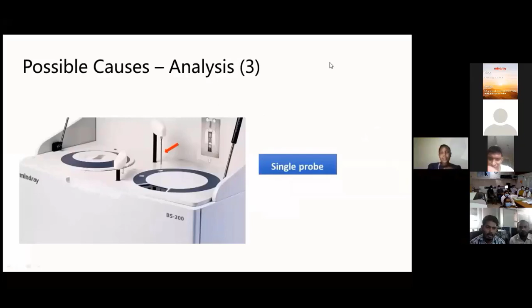There's always one who knows better than you sometimes. So we sought help from the distributor engineer. But no fault was found on site instrument checking. The instrument was okay, calibration okay, everything okay. Now, the engineer noted that the detergent was not original. It seemed the quality was not okay, and therefore he recommended that we get a Mindray detergent and use it and see. So we really wanted to fix it.